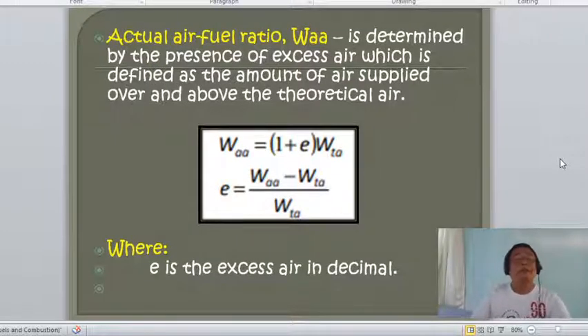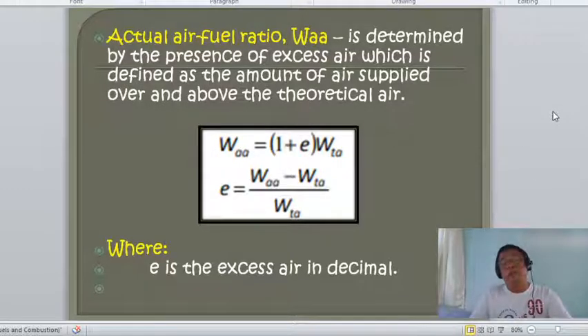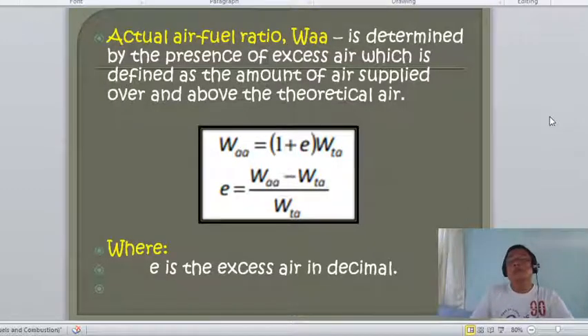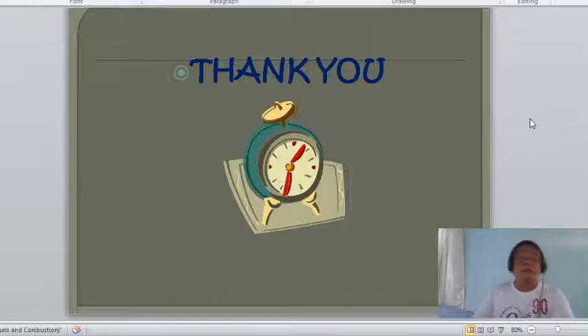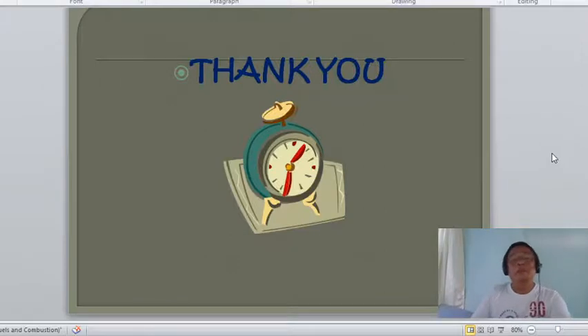The actual air-fuel ratio is obtained by multiplying the theoretical air-fuel ratio by (1 + excess air fraction E): W_actual = W_t × (1 + E). Thank you very much class. We have now discussed several important formulas for calculating fuels and combustion.